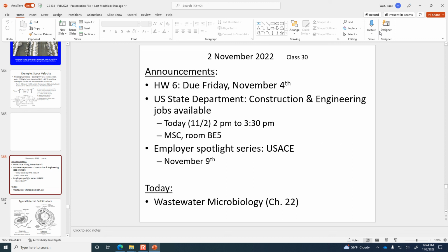The other thing that was mentioned is MLSS, mixed liquor suspended solids. That's the concentration of bacteria in the aeration basin. So it's another parameter related to the F to M ratio, which is, what concentration of bacteria do you want in the aeration basin? In a given liter of water, how many grams of activated sludge should there be in order to break down the waste? And then there's one other parameter that it didn't talk about, but it hinted at indirectly.